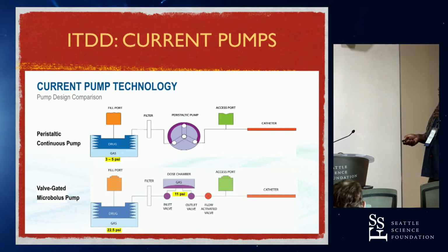So this valve, as I understand, is the key to how medication is delivered. It's not delivered in that constant peristaltic dribble. Based on the concentration of your medication and the dose you're delivering, those two known factors determine how long this valve is open. The length of time open then delivers your medication pretty forcefully, but it does have a velocity check. This flow activated valve, if it were to see the medication moving through too rapidly, would close, preventing that medication from being delivered. But this medication is now delivered in much more of a bolus format through the catheter. And the Flowonix pump does also have the catheter access port.